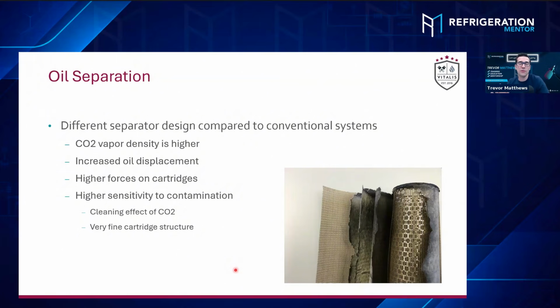Usually, what's great about CO₂ systems too is there are pressure transducers everywhere. But if you're going to do it with gauges on this, you need to use high pressure hoses because, like Jonas said, it could be 100 bar, 1450 psi. So make sure you do that. Now, if it's a 25 psid differential, that's another issue. You know what I mean? That means we're 100% clogged up. So I think it's a low differential, 2-3 psi, 0.3 bar maybe, that you should have regularly, right? Is that around the right range, Jonas?